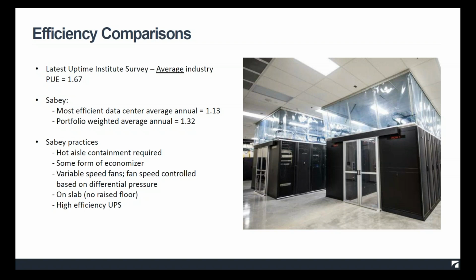Another practice that we've been doing since 2008 is we build on slab. We have no raised floor, and that simplifies management. And this kind of goes back to the first bullet that you see there, the hot aisle containment required. If we didn't require hot aisle containment, we would need some means of getting the air right in front of the server racks. By using hot aisle containment, we can simply flood the room.